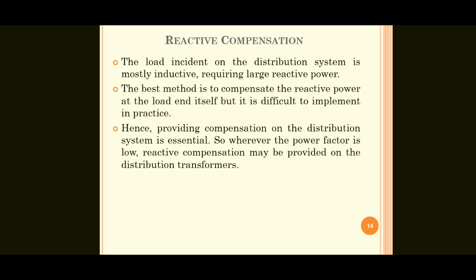So what is the procedure? Place the capacitors. Then automatically the power factor will improve. So it compensates the lagging power factor produced by the reactive load, meaning inductive loads. These capacitors compensate the reactive load, so the power factor is improved. Once the power factor is improved, the cost per unit is low and the drives run very efficiently. The efficiency is good, but reactive compensation is not that easy. It is not so easy a process. Adjustment of capacitors or inductors is always a very difficult situation.